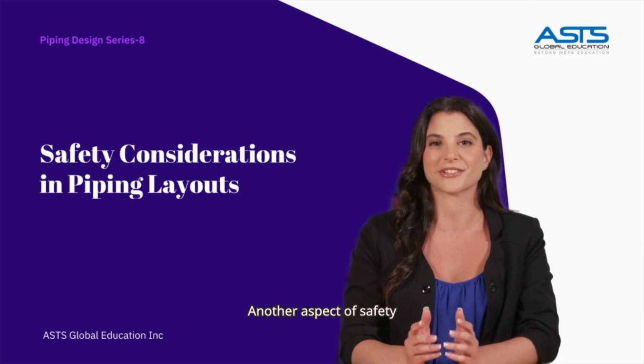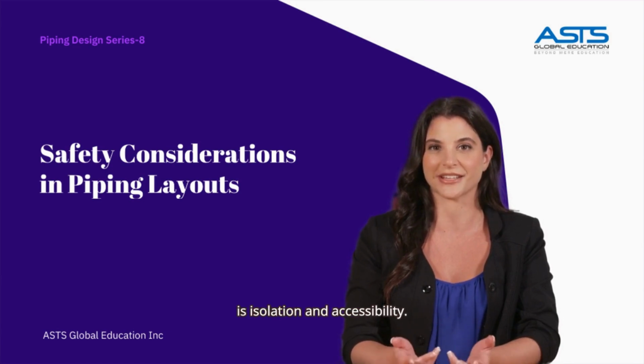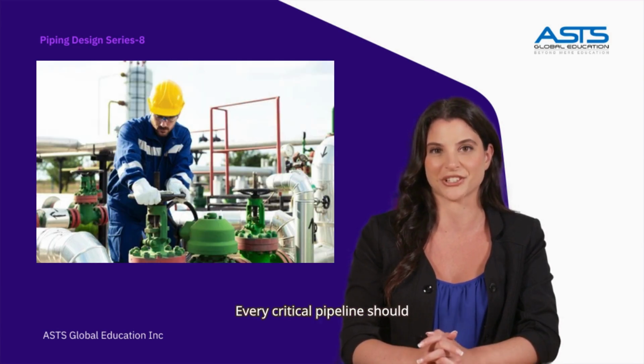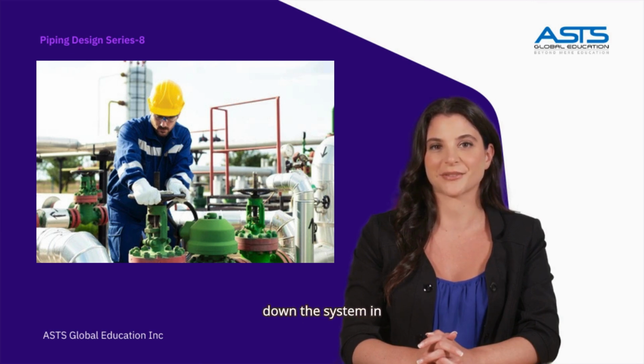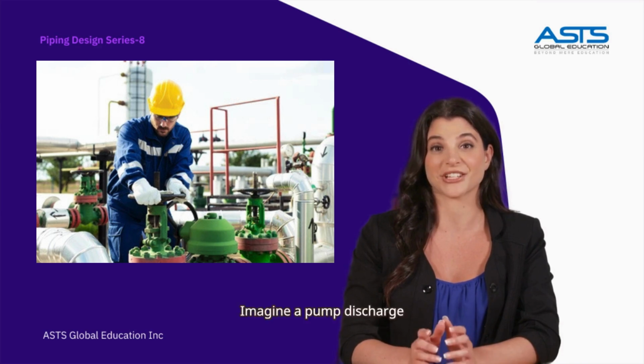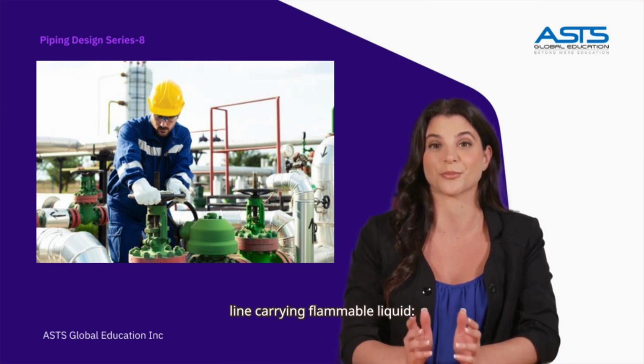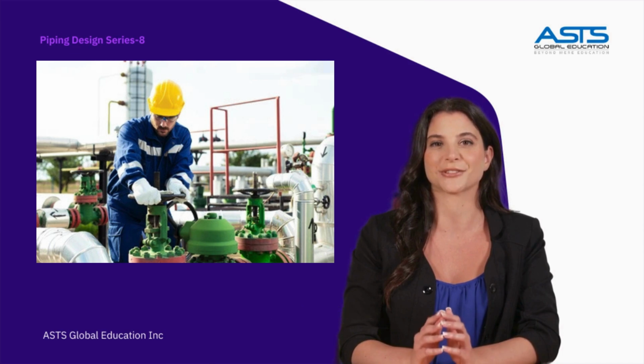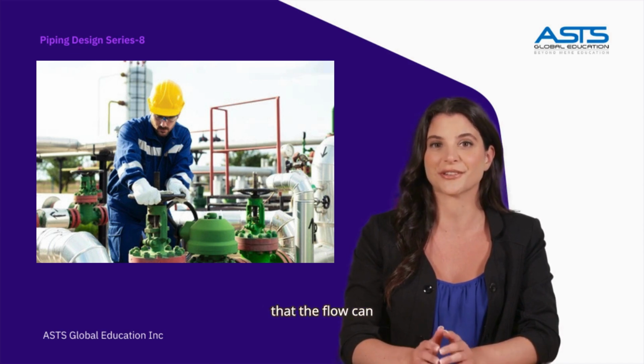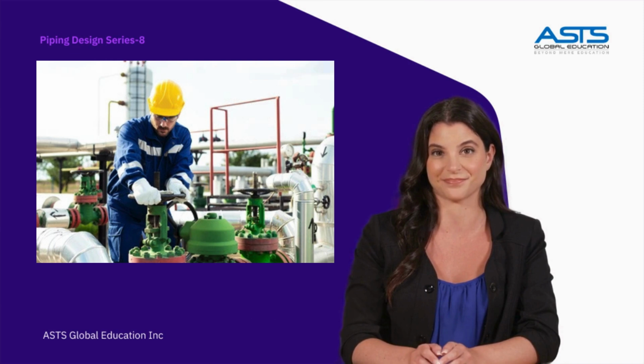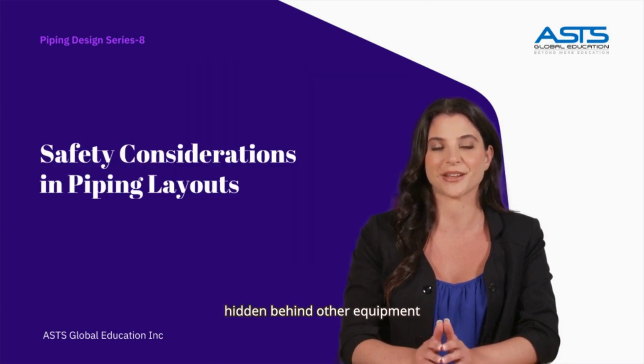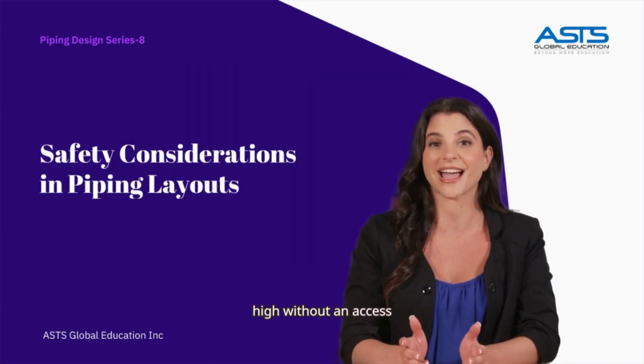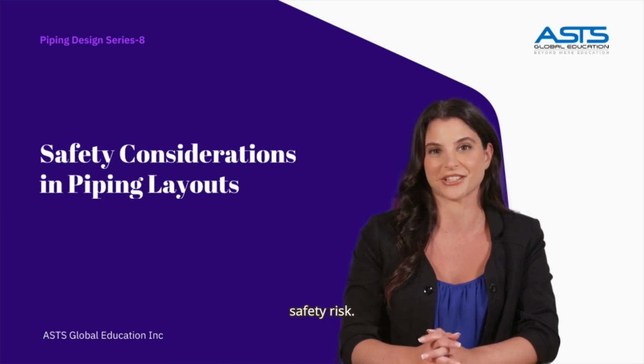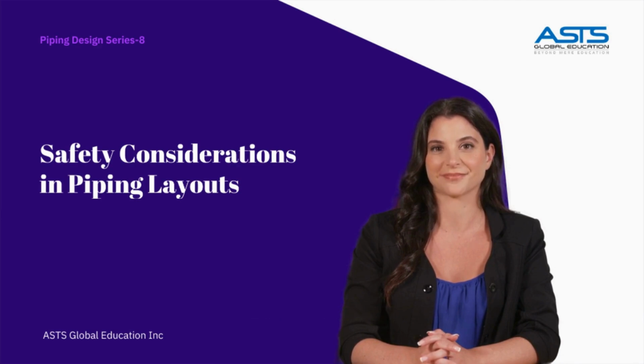Another aspect of safety is isolation and accessibility. Every critical pipeline should have valves placed in such a way that operators can quickly shut down the system in case of emergency. Imagine a pump discharge line carrying flammable liquid. If the pump fails, the valve should be easy to reach so that the flow can be stopped immediately. If the valve is hidden behind other equipment or is placed too high without an access platform, it becomes a safety risk.